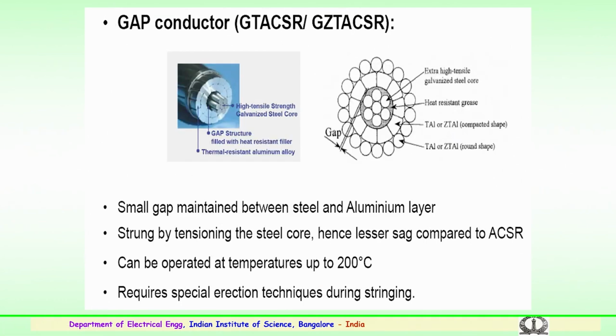So, the third is the gap conductor, GAP, which has a small gap. You can see the construction of the conductor here. This is the extra high tensile galvanized steel core. It is followed by a heat resistant grease surrounding it. Then the compact size conductors are placed, and finally the round type of conductors are at the periphery. So, you can see the high tensile strength galvanized steel core and the gap structure, and finally a small gap in between, where this gap structure is basically filled with heat resistant filler.